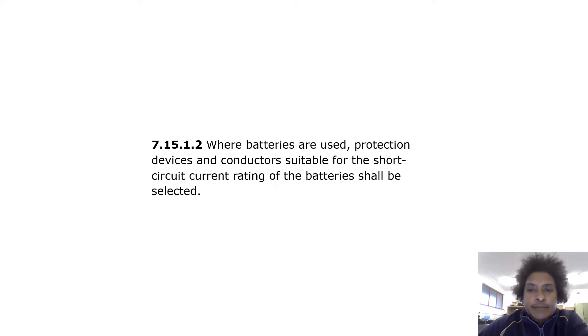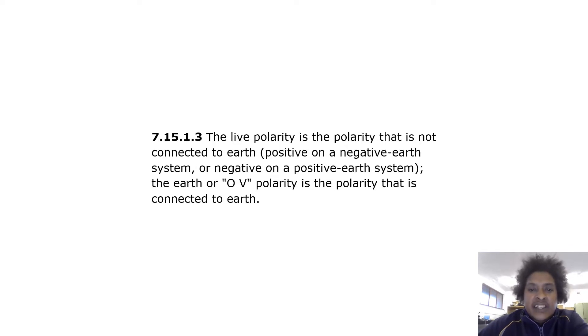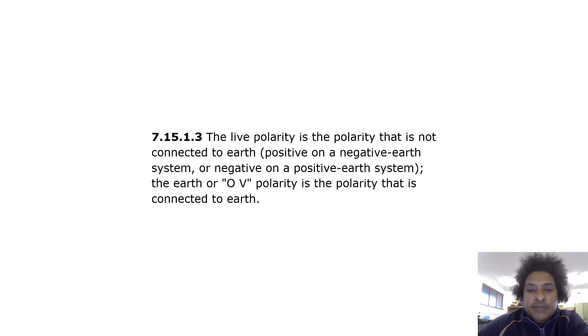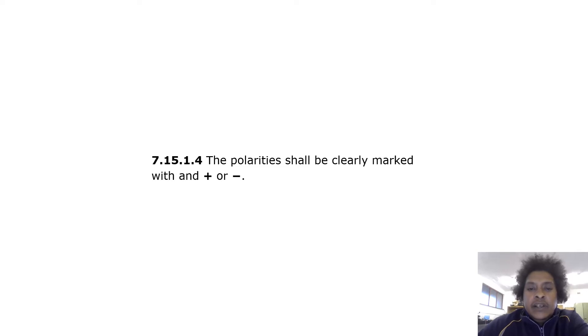The live polarity is the polarity that is not connected to earth — positive on a negative earth system, or negative on a positive earth system. The earth or zero voltage polarity is the polarity that is connected to earth. The polarity shall be clearly marked with a positive or negative sign.